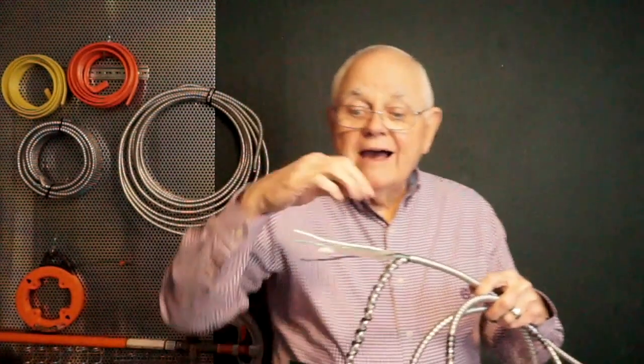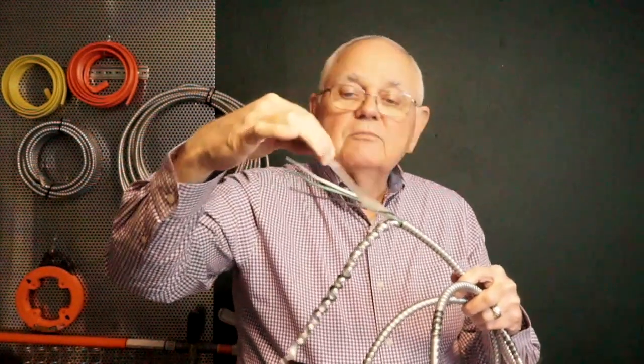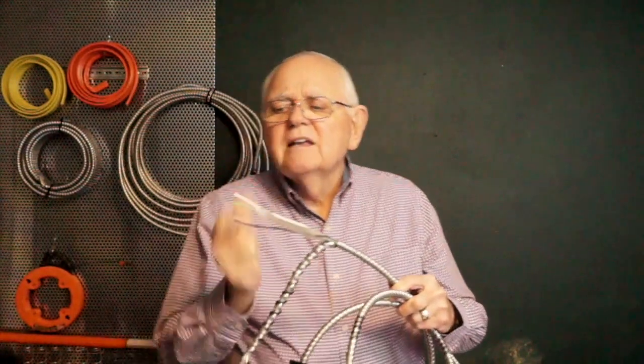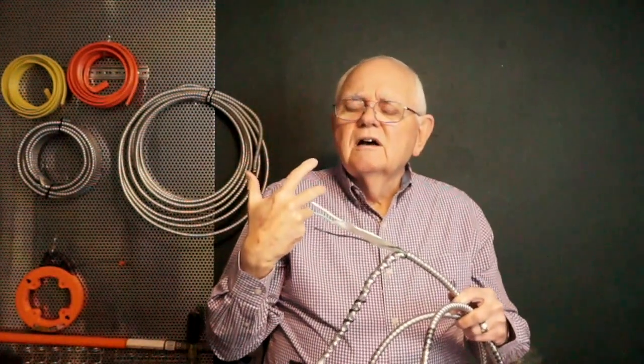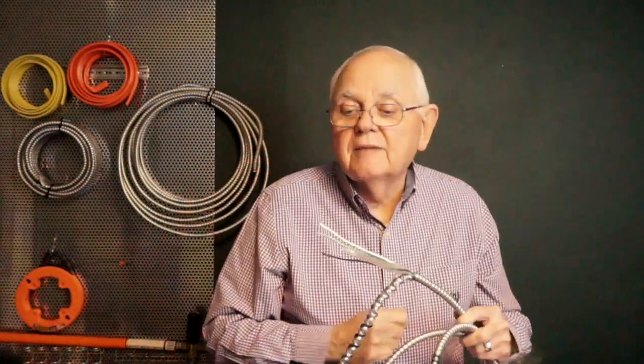Then let's start talking about the conductors on the inside. First of all, our conductors are bound together with this transparent, in this case, it's a plastic type, or Mylar is a trade name you'll hear on it, type sheath that binds the conductors together and holds them together. The conductors can be either number 18 or 16 copper or nickel plated copper, and aluminum sizes are going to be size 12 and on up from there. So I can have 18 or 16 copper, I can have copper clad aluminum, and of course the nickel plating.